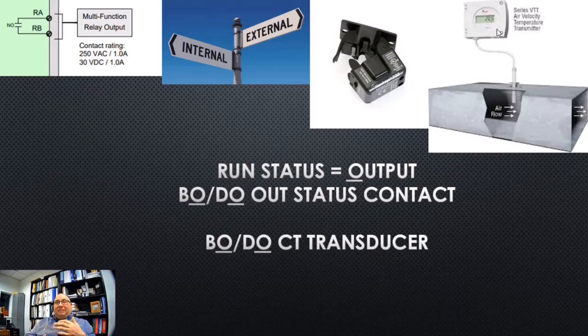And what could happen is we could actually start the cooling process, and it's called equipment staging, without truly knowing whether or not the drive is truly running. So the way to know the drive is truly running is that it's truly moving airflow. And one way to truly know it's moving airflow is to put a velocity sensor in. So then we know we got up to our target of 1 inch of static. Then let's start staging up our compressors and opening up our liquid line solenoid valves and starting the direct expansion cooling process. If we didn't know that and we based it on a CT or a relay coming from the drive, we can initiate a cooling sequence even though we're not moving air, if you know what I mean. So external, and whenever possible, a transmitter that would measure air velocity is the right way to go.